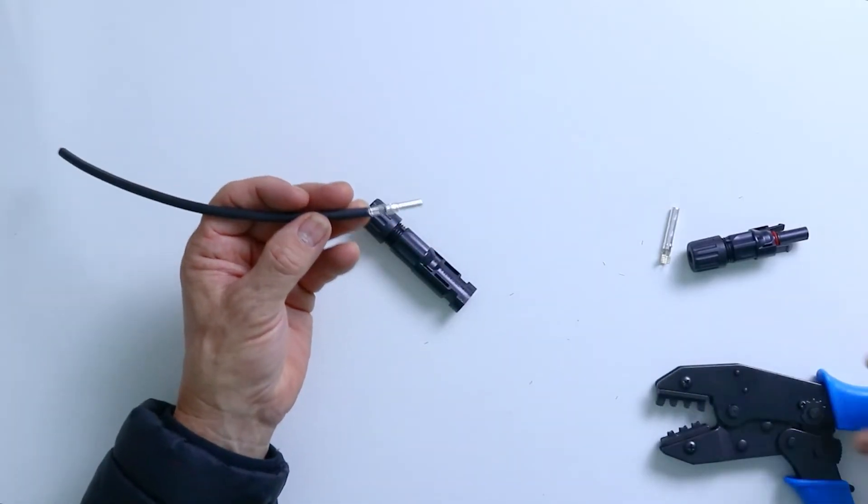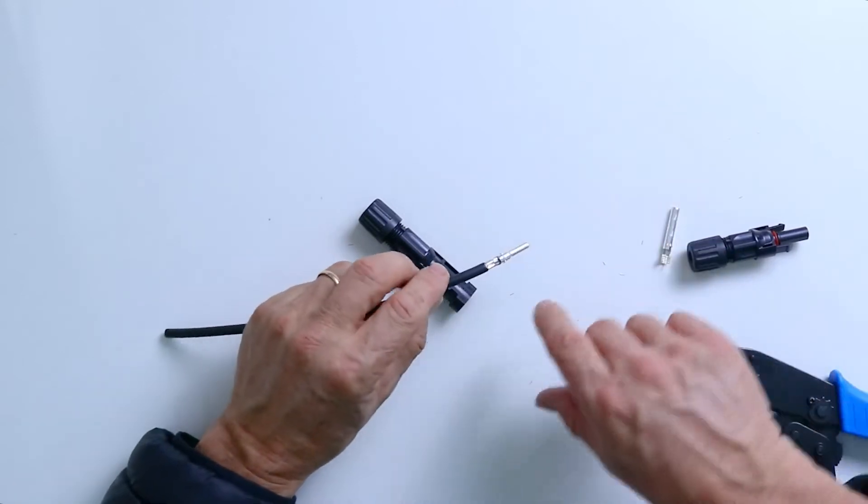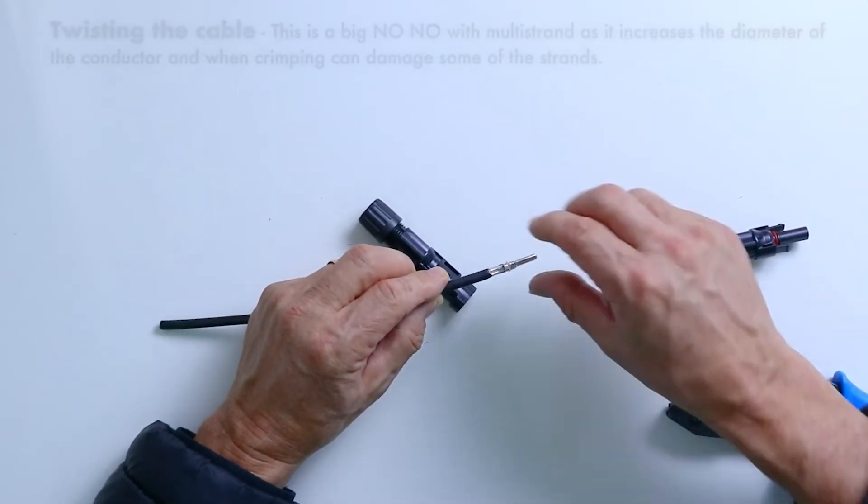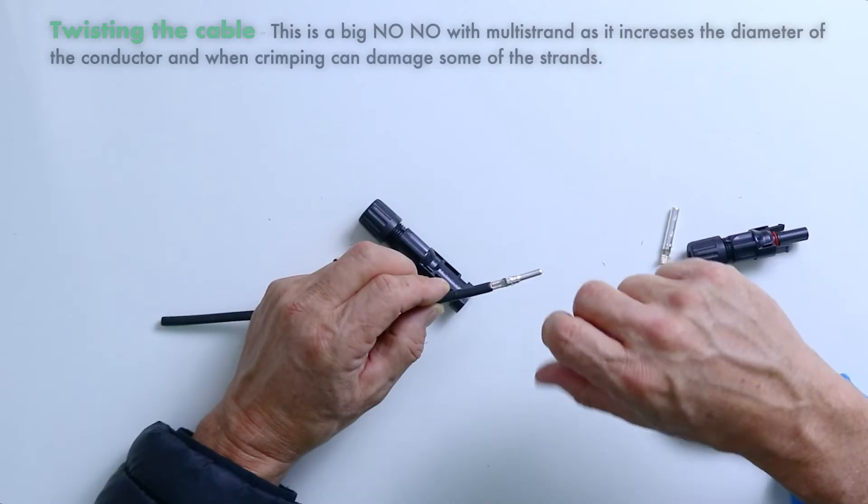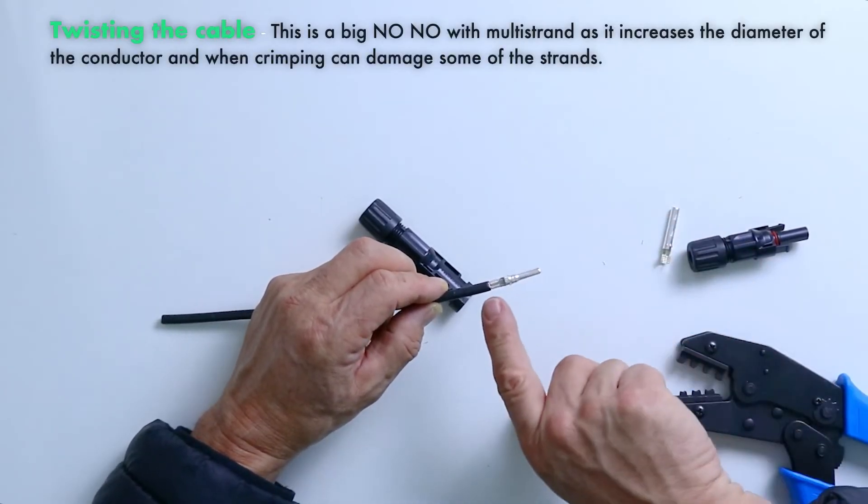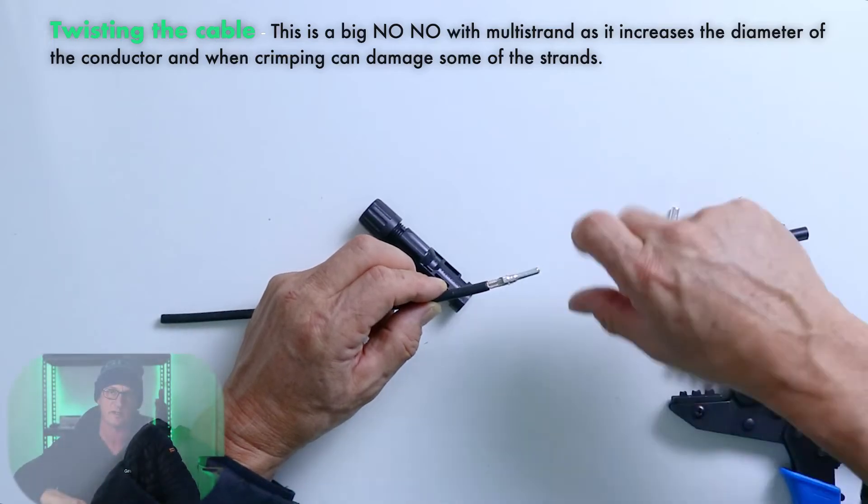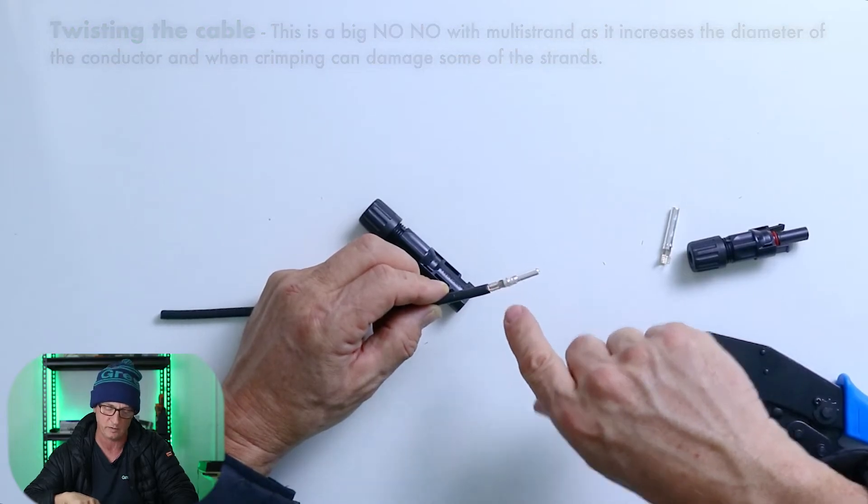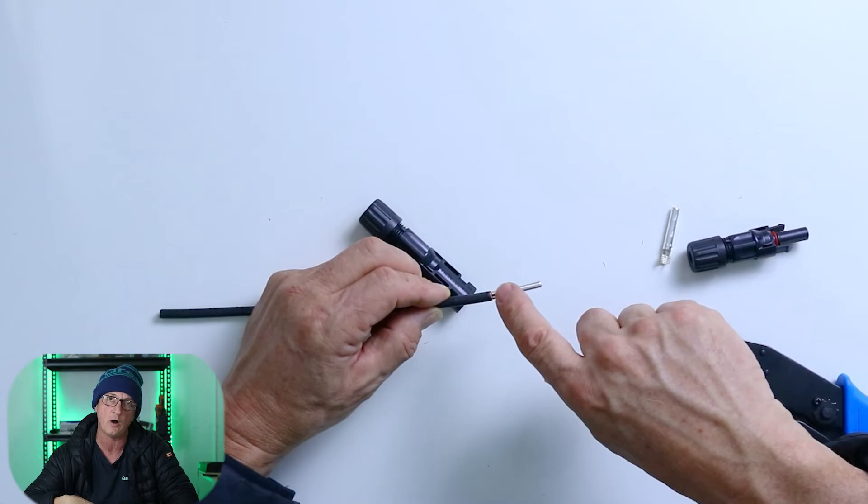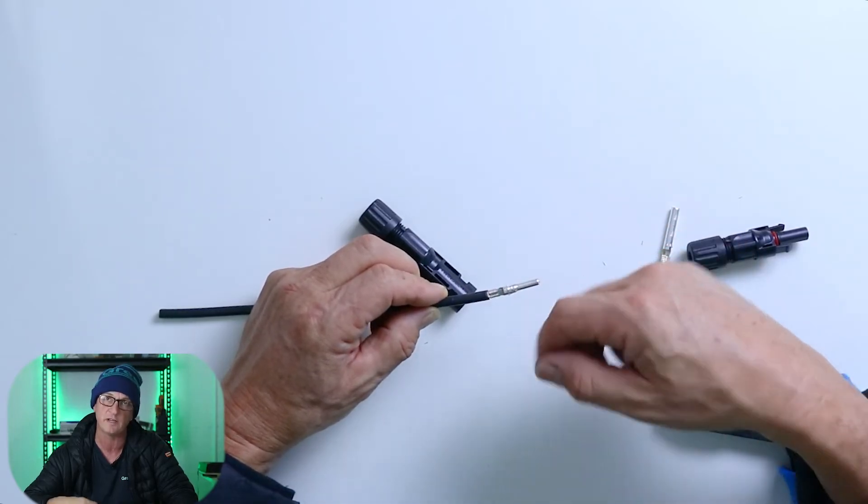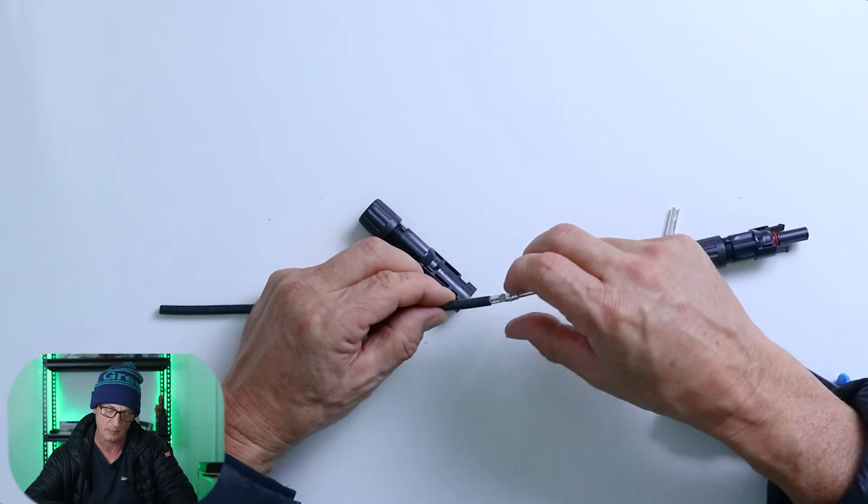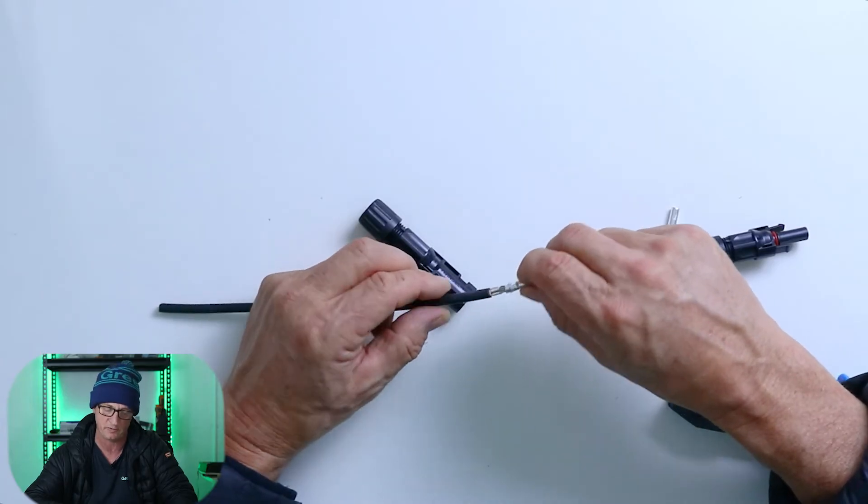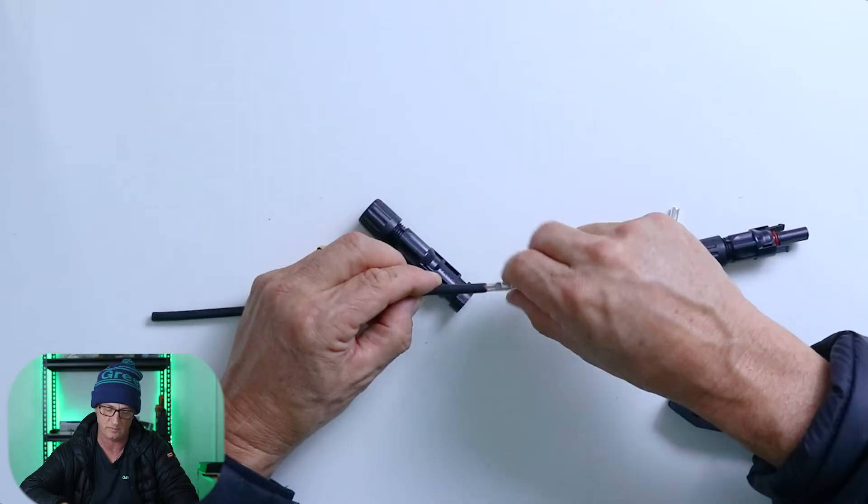So what happens here is that it crimps down onto the actual strand, this multi-strand solid DC cable that's tinned. With this cable, what you don't do is twist it. Now some people, when they actually take the insulation off and they use a pair of pliers, they twist the insulation. And this actually twists the strands. Now the rule of thumb is, if this is not twisted in the first place, don't twist it. When you start twisting the strands within the cable, it actually increases in diameter. And when you come down on the crimp, you can break some individual strands. So it's very important not to twist this cable.